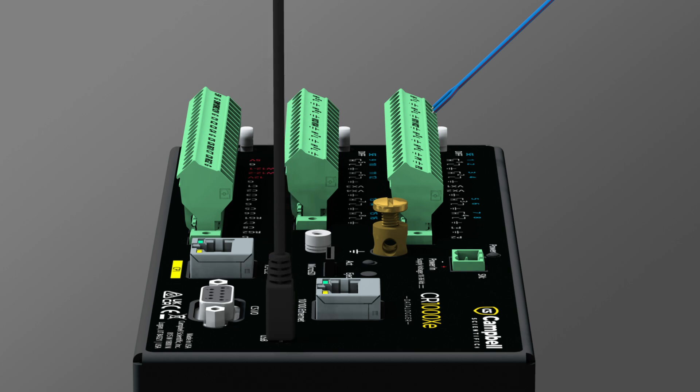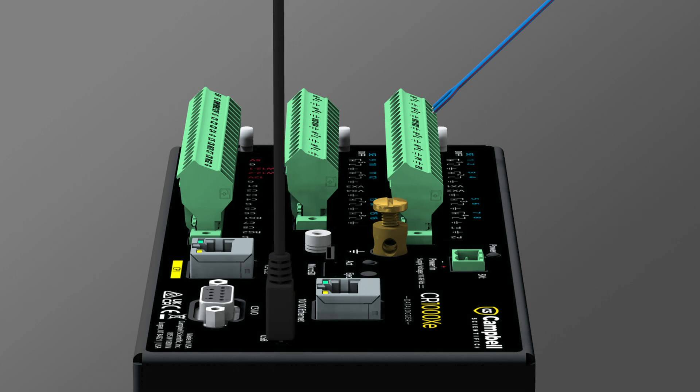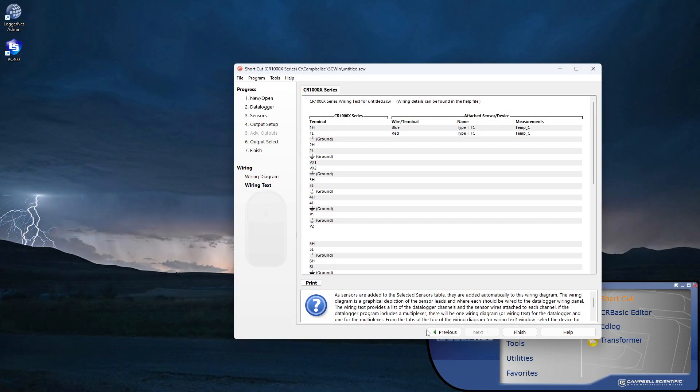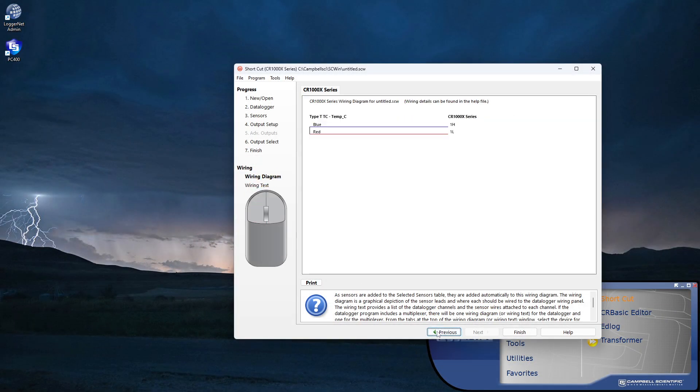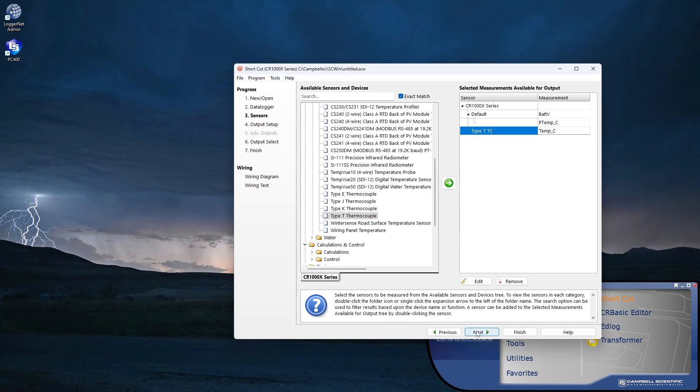When done, reapply power. Remember that a 12-volt power supply is needed to make measurements in the field, but power over USB is sufficient for data logger configuration. When I'm done adding and wiring sensors, I click Next.